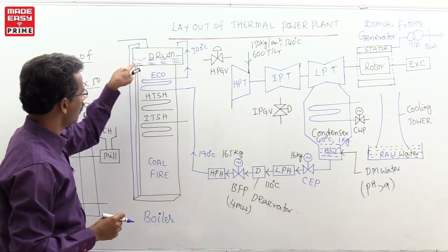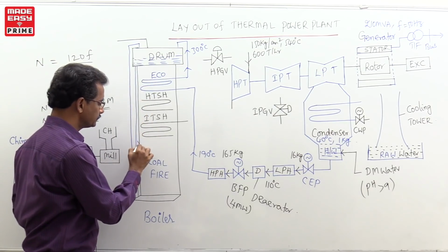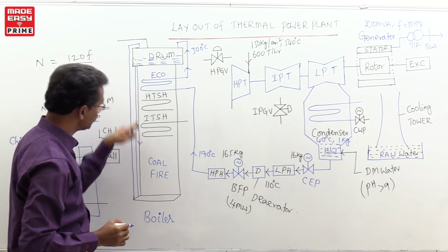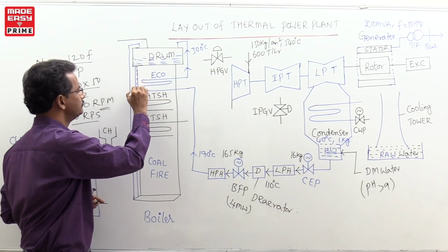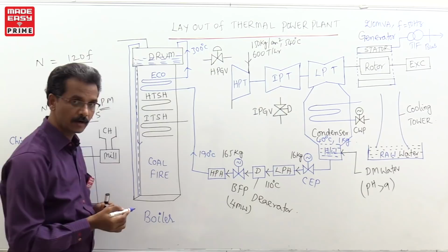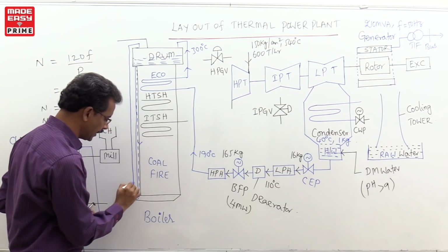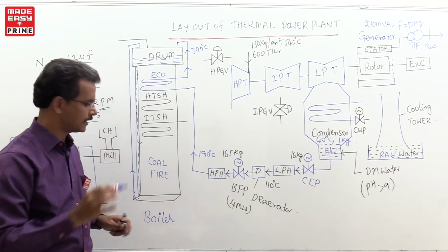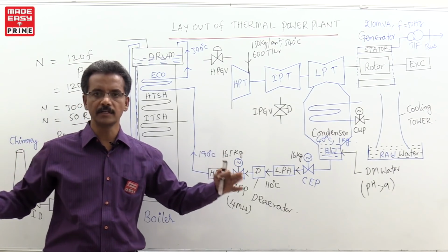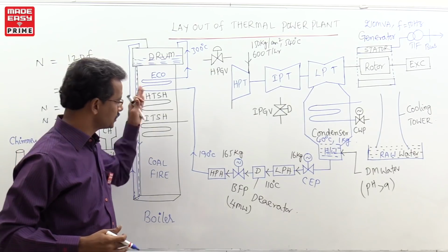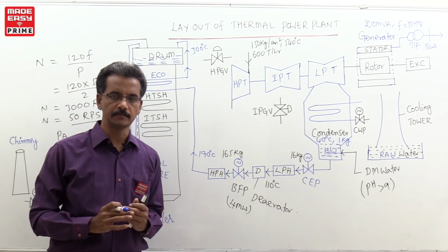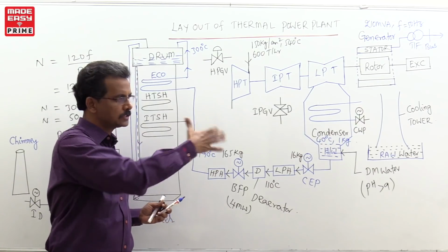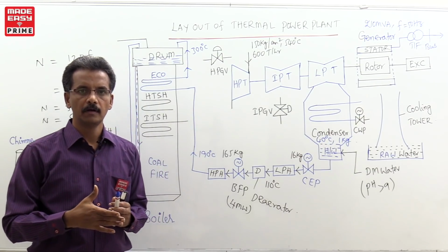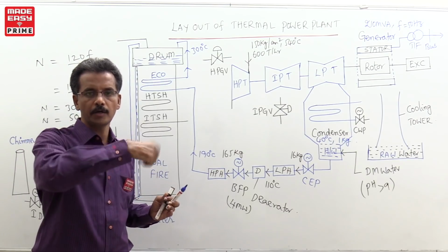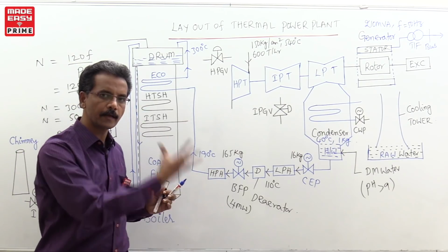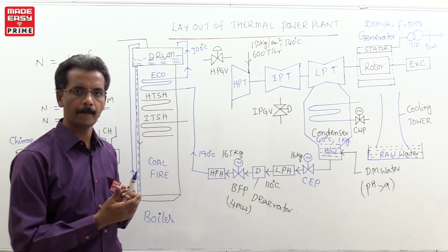Now, the water will circulate. This is the water path, you can imagine. Naturally, water will fall down, and this water is now raised. During this process, now you can imagine this boiler. In the boiler, imagine that tubes are there. Imagine one room. In this room, the walls, whatever is there inside the room, think of as water tubes. That means steel tubes, metallic tubes are there, and inside them water is flowing.